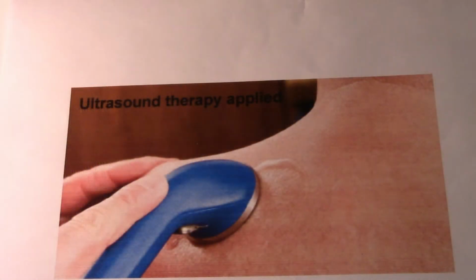Ultrasound therapy is applied using a piezoelectric transducer within the head of the wand probe that is in direct contact with the patient's skin. Gel is used on all surfaces of the head to reduce friction and assist in transmission of the ultrasonic waves. The ultrasound can be pulsed or a continuously transmitted wave. Therapeutic ultrasound in physical therapy is alternating compression and rarefaction of sound waves with a frequency of 0.7 to 3.3 megahertz, 3.3 million cycles. This is a picture of ultrasound being applied. The head can be smaller or larger depending on the equipment.